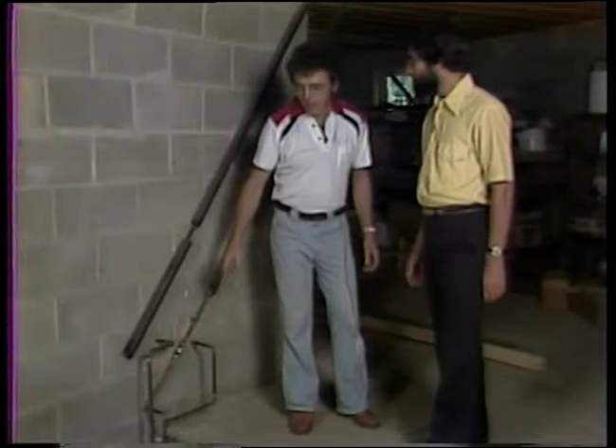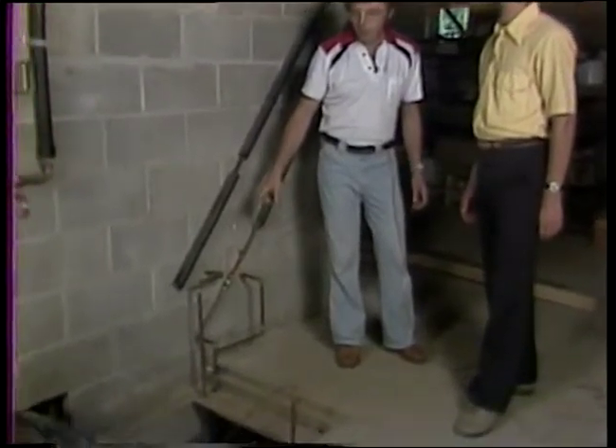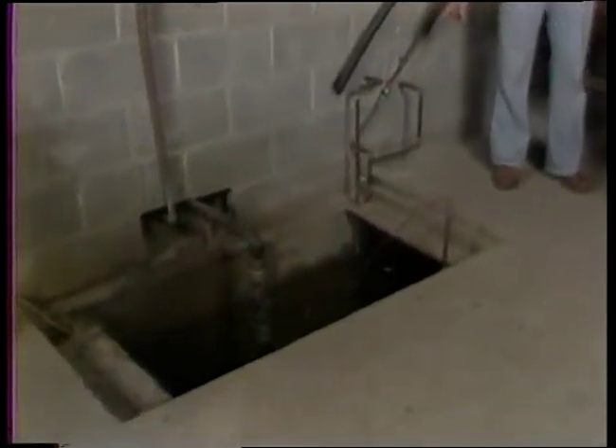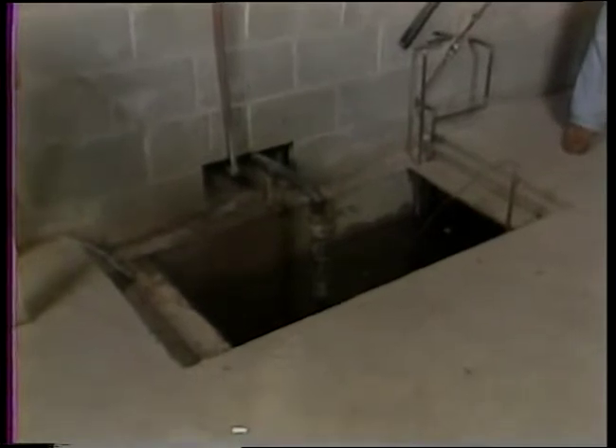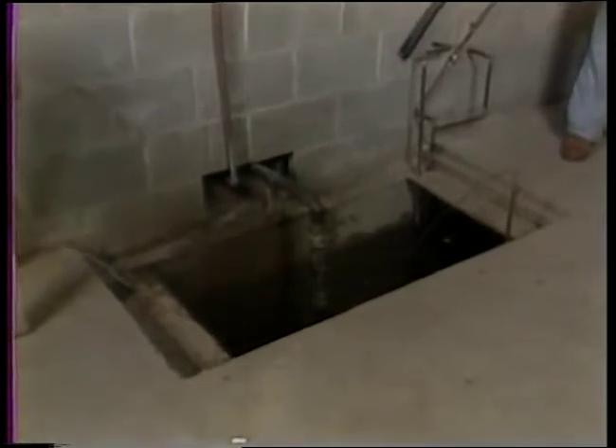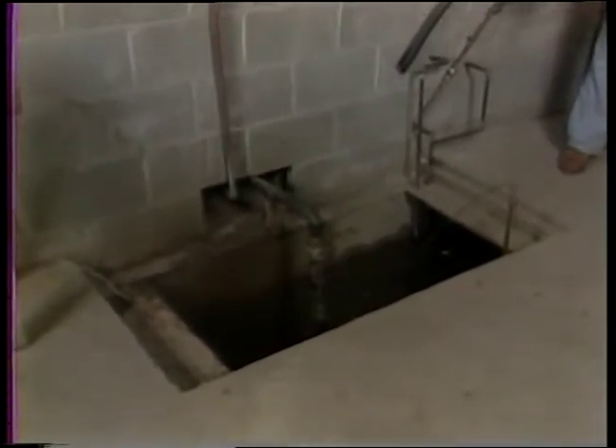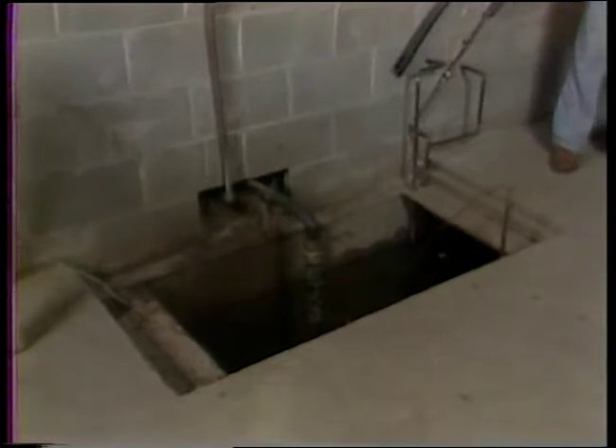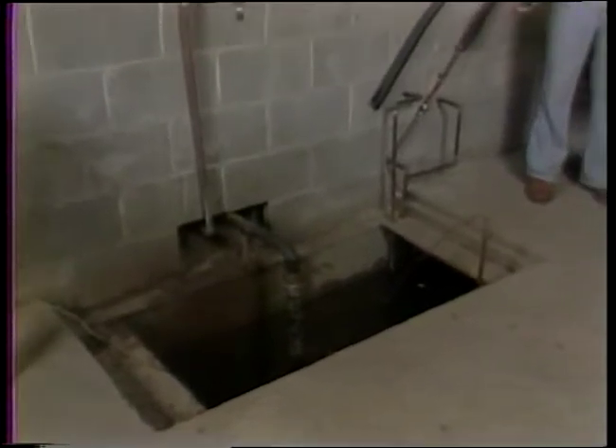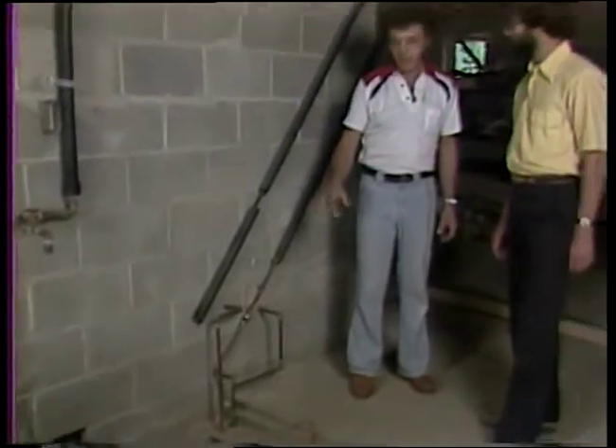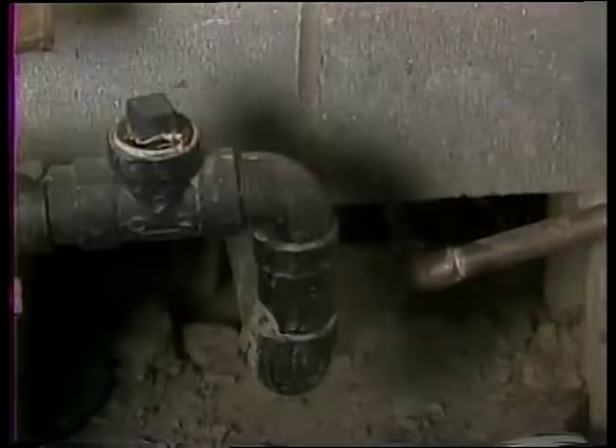This is a poured concrete tank. It's about 10 feet deep, roughly 12 by 12, with 8 inches of styrofoam insulation on the outside, and holds about 12,000 gallons of water. This is the water that we use to store the energy that the heat pump takes the heat out of that is later transferred to the house.